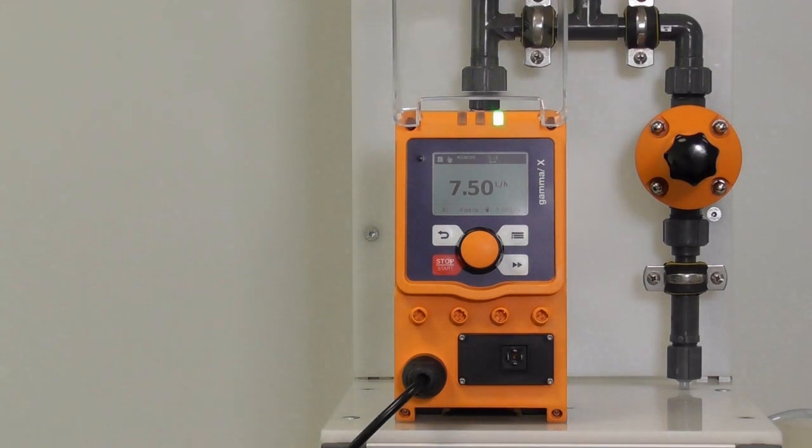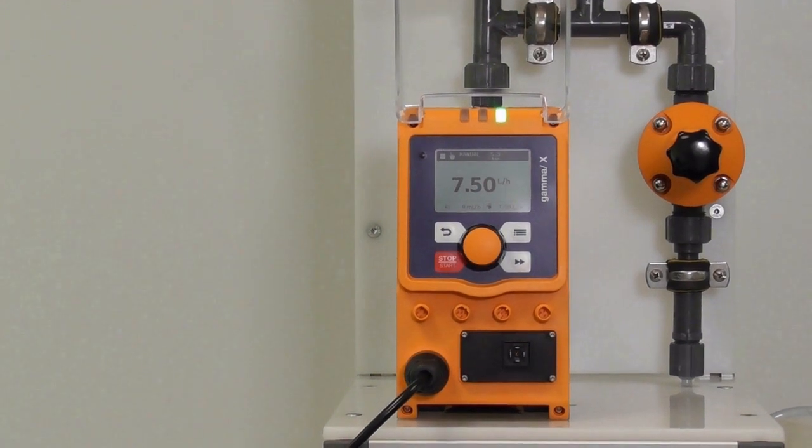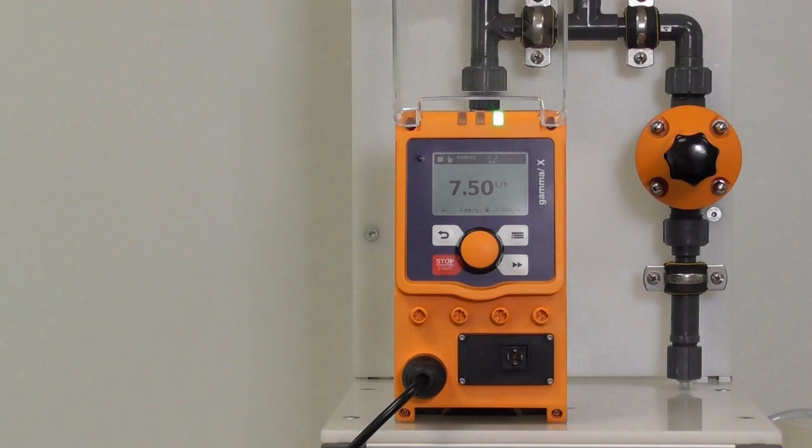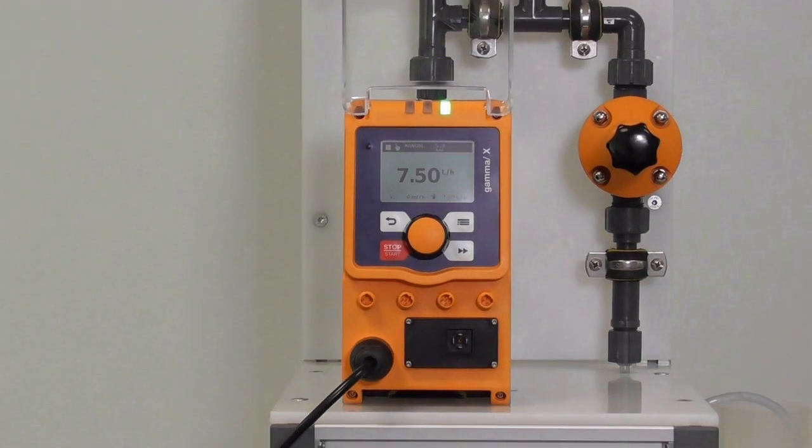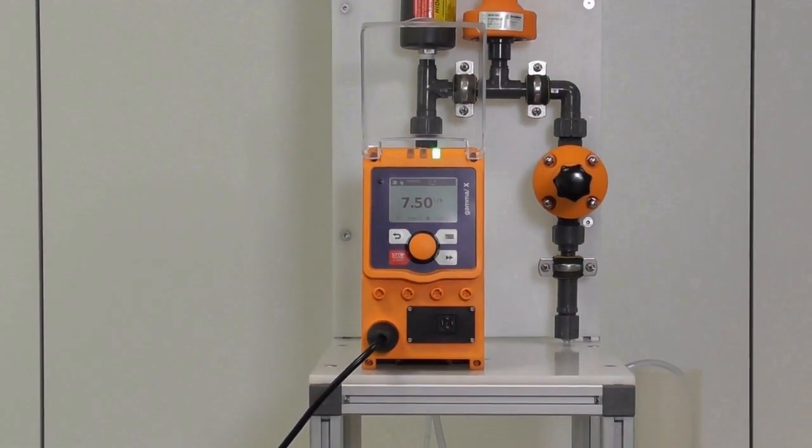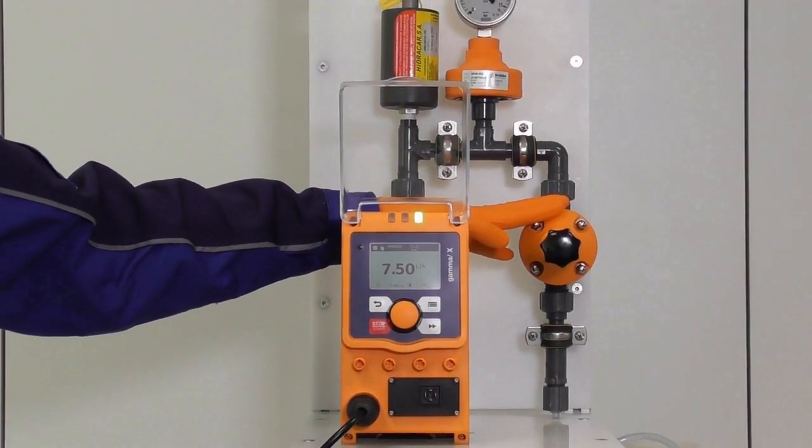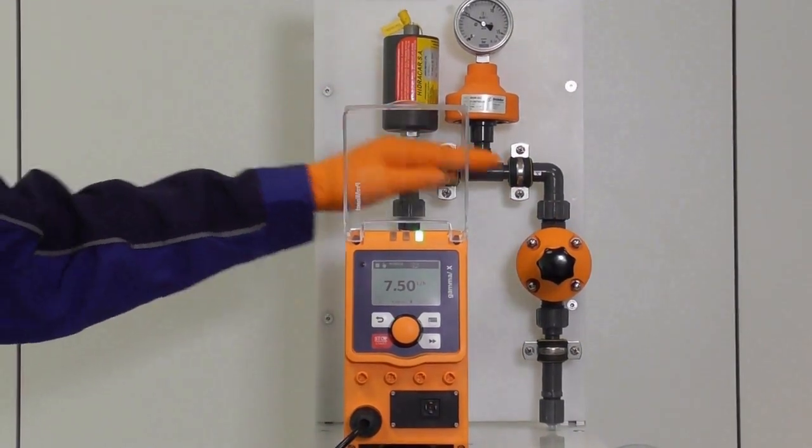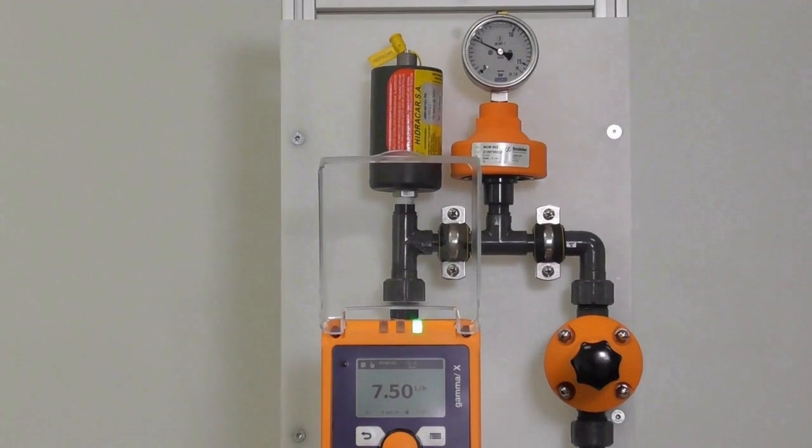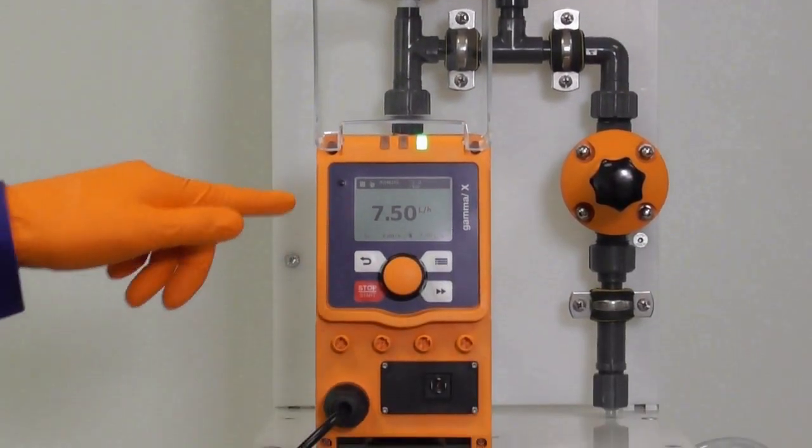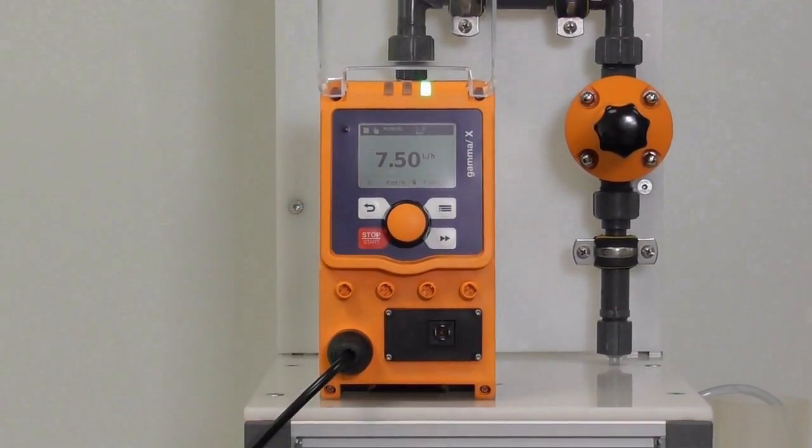When you do the calibration, it is really important to calibrate always from the suction side. So put a scale or a calibration vessel on the suction side and then you start a calibration process. This is very important because when you calibrate via the pressure side, you do not get such accurate values as you have things like a pulsation dampener or a back pressure valve, and these are causing bad dosing results.